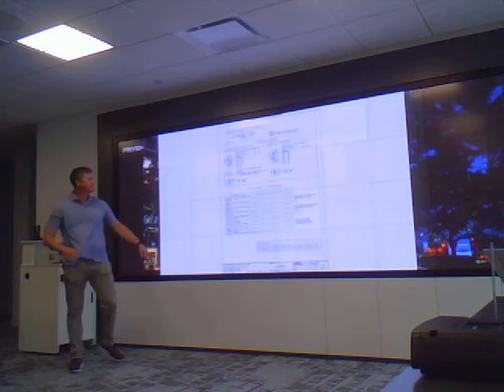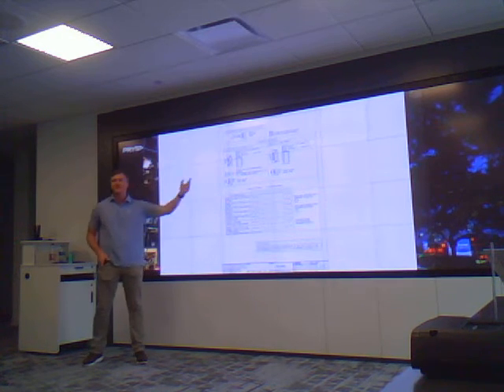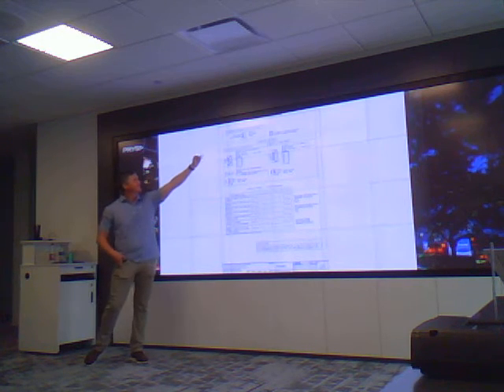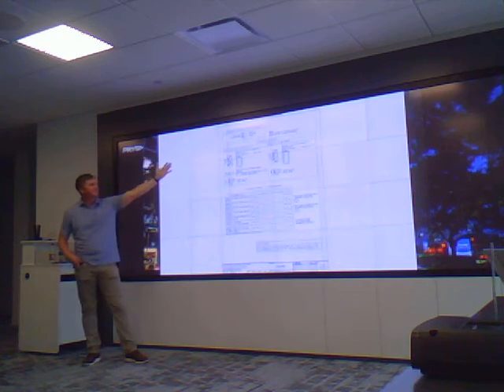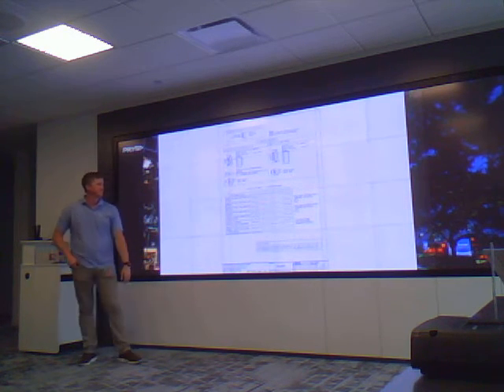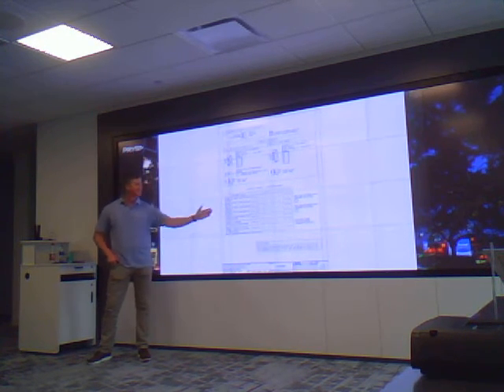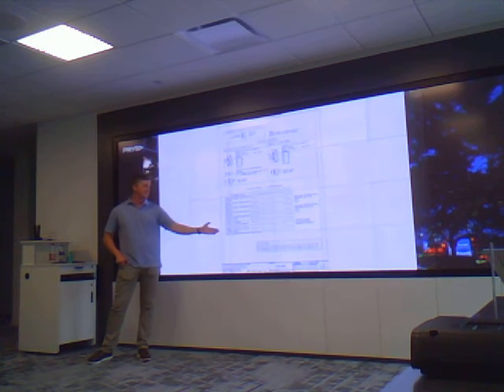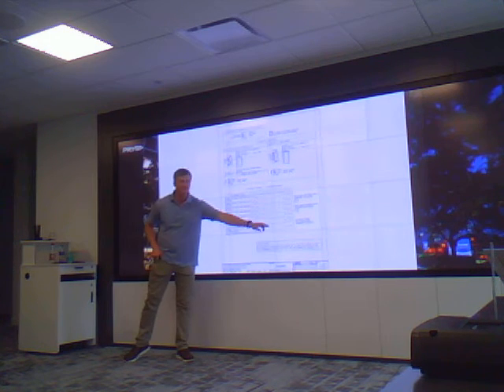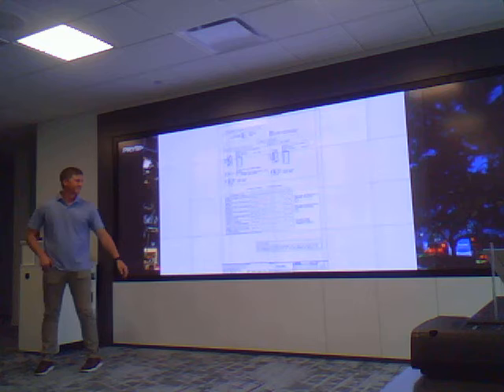So this is just your dip switch settings. This actually shows you how to set them for the heat pumps. Like he was saying, you tell it to cool and it starts heating when it's reversing. So you go up to your dip switches and flip it. I think it's B that goes on for that. It turns on, but you look through here and it tells you the different modes: heat pump, multi-stage with this, or multi-stage, single stage, standard multi-stage. Everything stays off for the first two, and the last one's on because it's multi-stage. So it's a good thing to reference back.